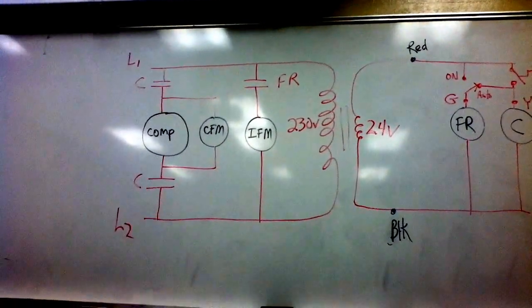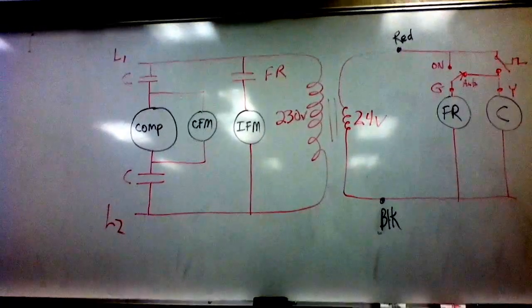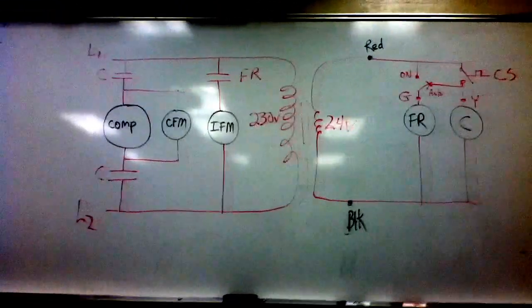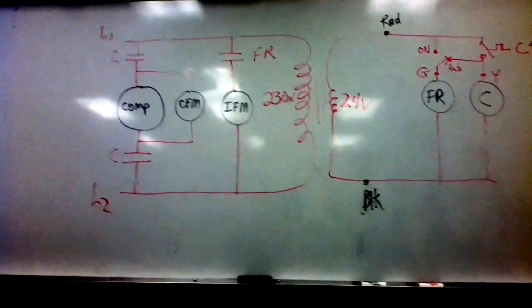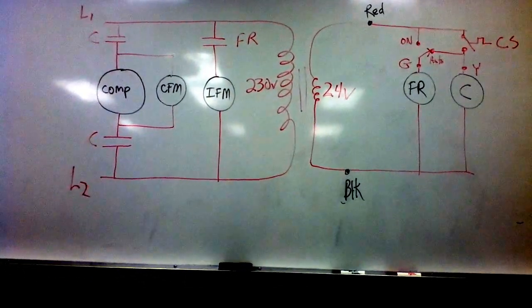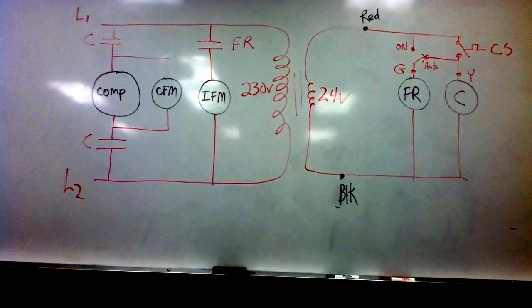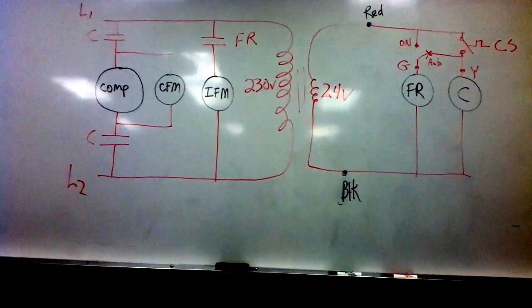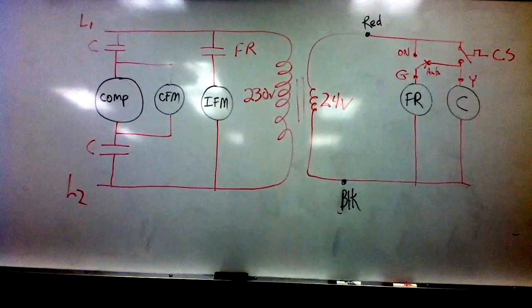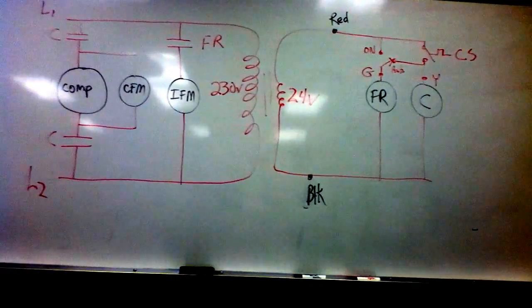As a customer option, there is a switch that's labeled on for the fan. When you turn it to on position, the fan runs 24 hours a day. The air conditioner will still come on and off as needed, but the fan runs to circulate the air. There is the basic air conditioning schematic. Does anyone not understand it as I've explained it?